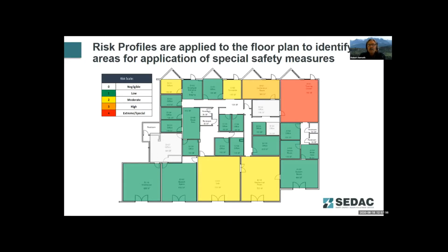What do we do if we own this building or we work in this building? We might want to tell that person, why don't you work from home? Or maybe that person wants to work from home, and all of a sudden that space turns green. We really don't need to do too much to that space. Now, Ty's recommendation of 800 ppm is very good. There's a lot of evidence that points to the fact that we should be going below what ASHRAE recommends at 1200 ppm.